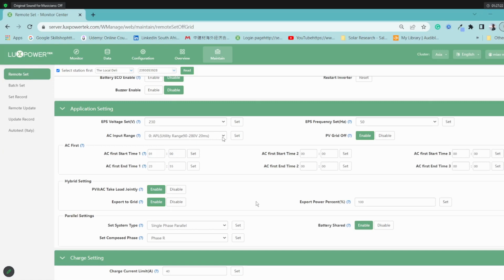Okay, so what we recommend from our experience is to just program it as a UPS, where the low voltage is a little bit higher at 170, the current is better, and the changeover is within 20 milliseconds, so it's more stable and it can reduce that delay. All right, and you might also have experienced, when Eskom trips or when it just comes back on and it has to take a load of, let's say, 1 kilowatt to 3 kilowatts of power, you will get a warning 28, which is EPS overload.